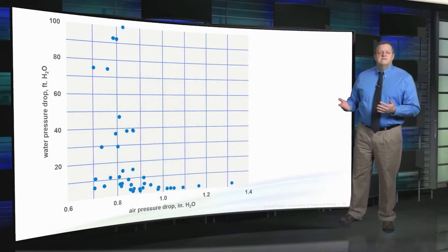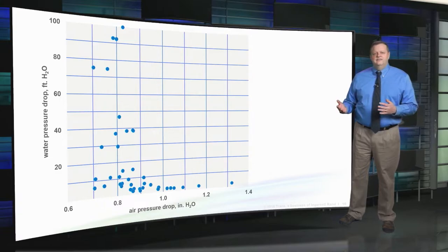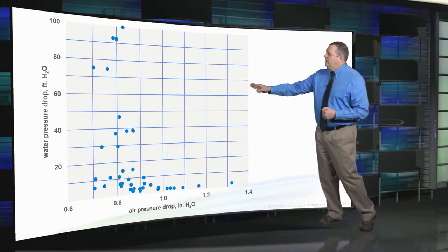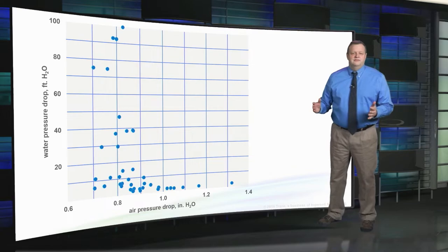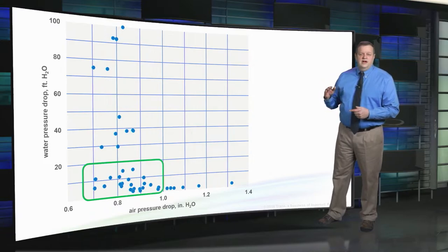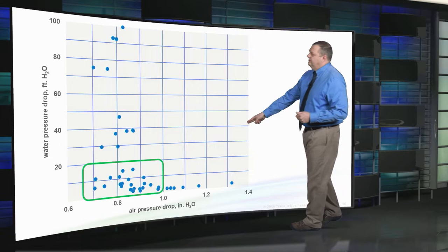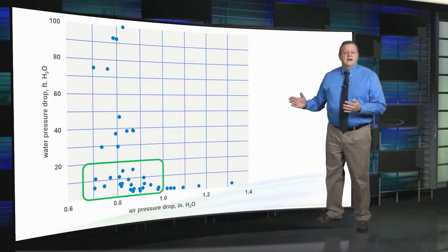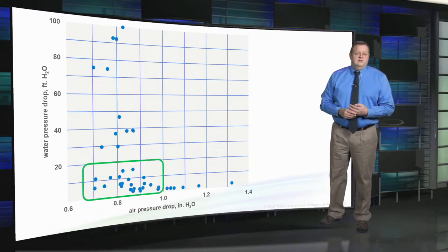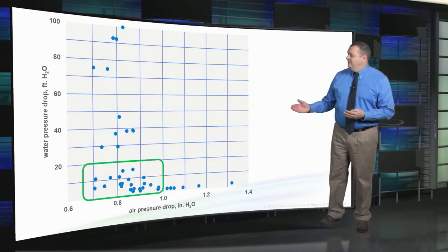To provide the required capacity, Trane's selection software gives 53 choices for this size air handler — different tube diameters, fin styles, circuiting options, etc. To simplify, let's remove the outliers. Plotting air pressure drop and water pressure drop for all 53 possible coils, we can eliminate those with the highest pressure drops and focus on choices in the lower range. For this application we have plenty of options. I'll also remove coils with 10 rows, since deeper coils can be harder to clean. And I'll remove those with water velocity lower than 2 feet per second at design conditions.